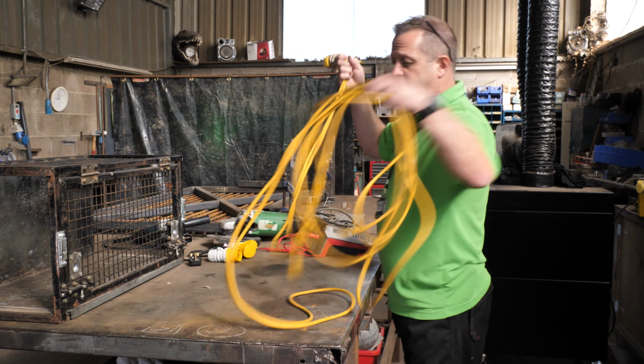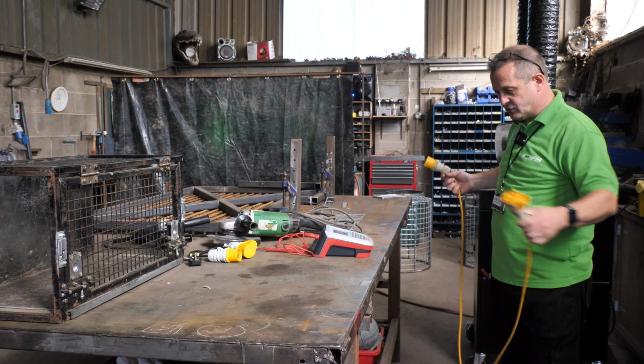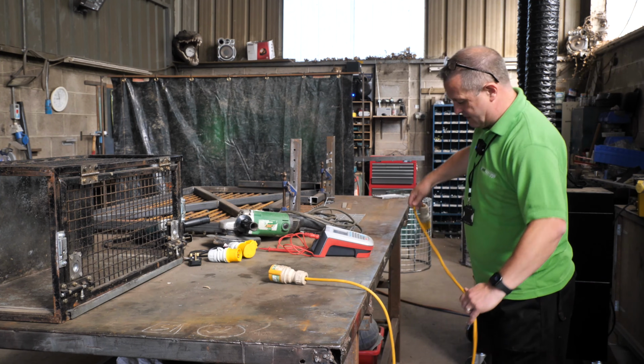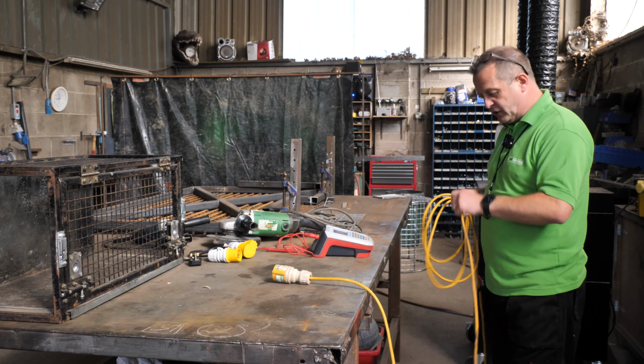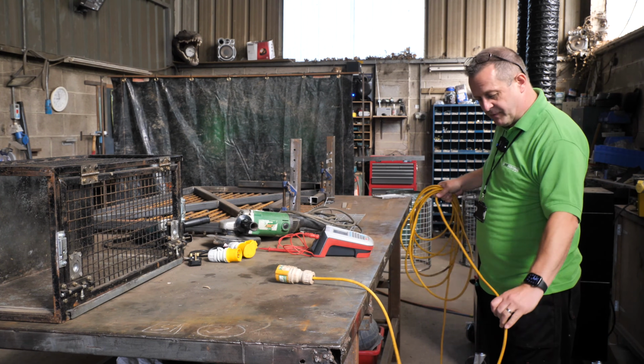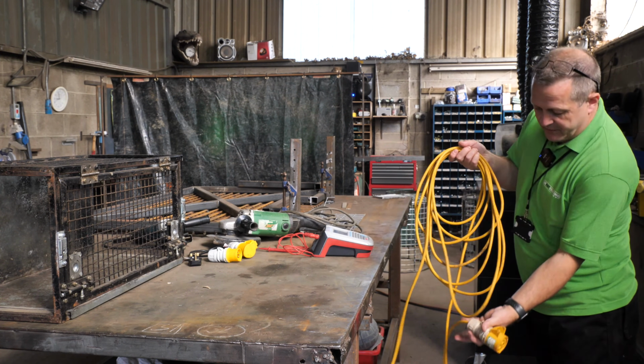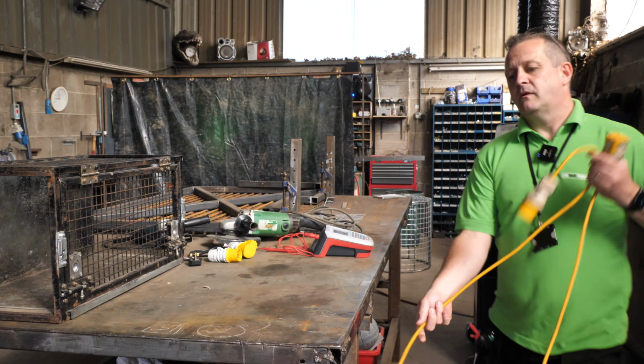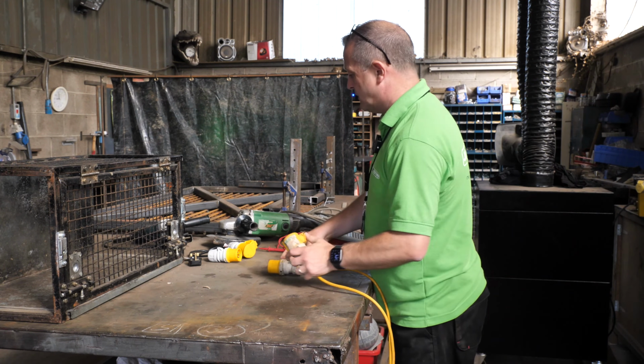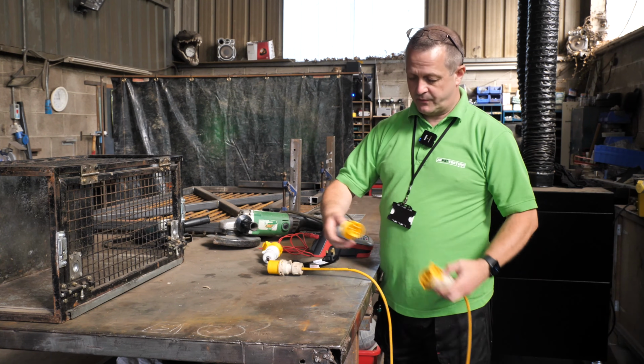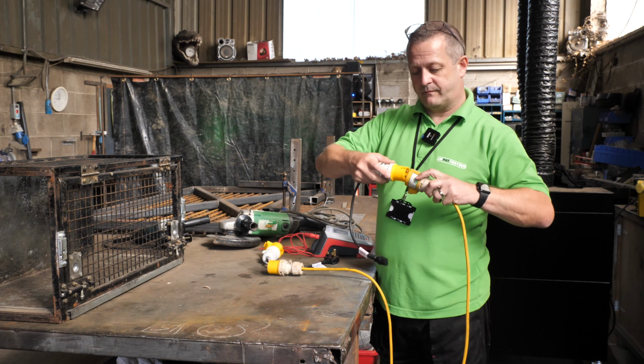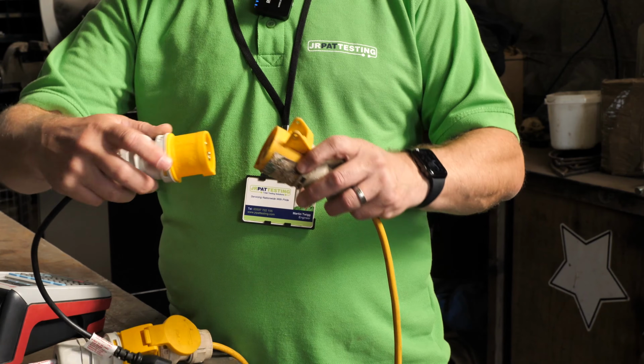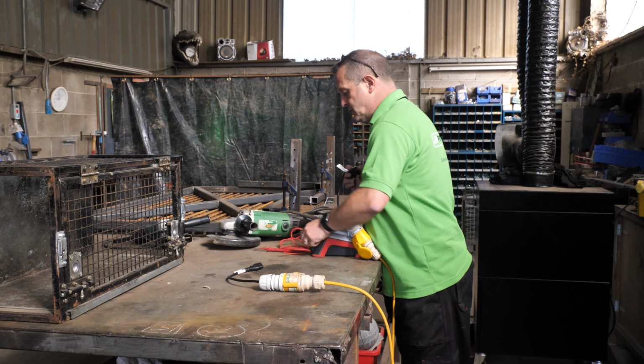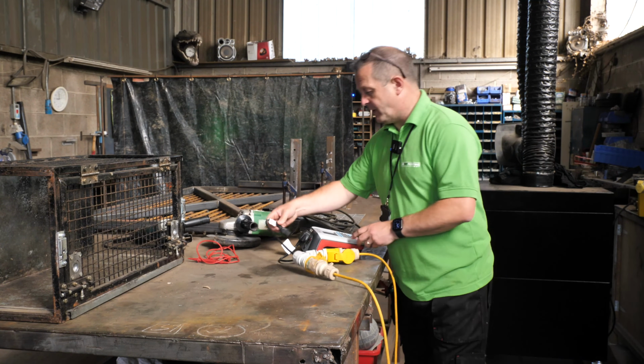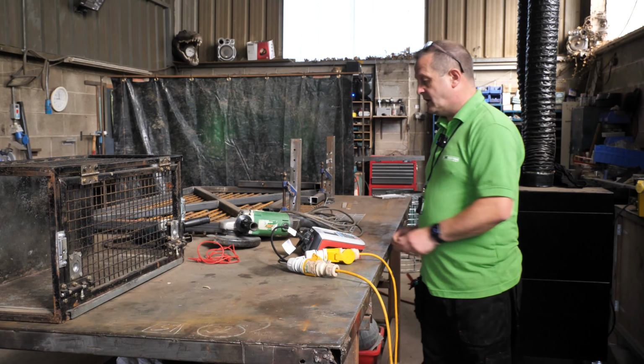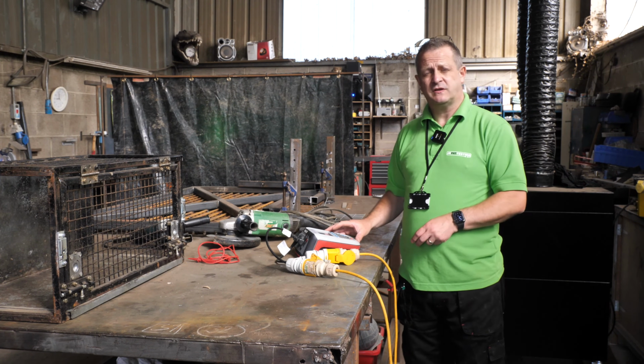So with cable, you need to be able to take it to its full length and make sure that it's in its order. Again, we're going to do a visual inspection, making sure that we've got no cuts or tears, exposed metalwork coming through. And I'm happy with that. So we're going to put the cable out, and then we need to make use of 2 adapters in order to conduct the test. They go in there as such. The plug part goes into the PAT testing machine, and the IEC part goes into obviously the IEC part of the PAT testing machine, and then we're selecting a class 1 110 volt test.